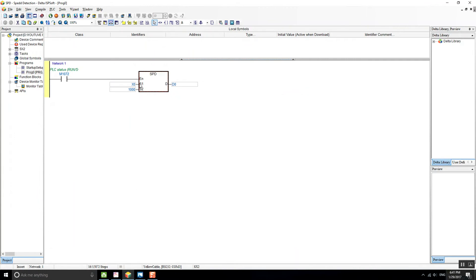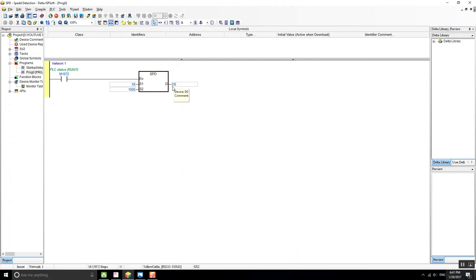The speed detection will be activated when M1072 is on. For S1 we're going to use X0, which is one of the high-speed inputs of my PLC. For the time I'm going to use 1000 milliseconds, so that's one second, measuring how many pulses per second. The result is going to be stored on D0.